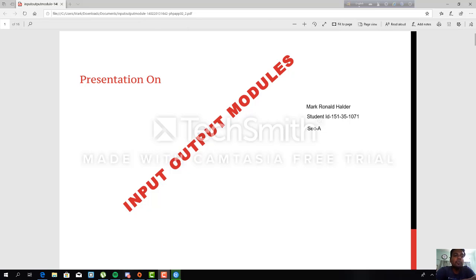There is a module called the SLC 500 combination. This combination works like this: each screw terminal will have a unique identifier called an address. Each field device input screw terminal will correlate to a status indicator. The status indicator will be on when the input point sees an input signal. The status indicator will have the same address identifier as the input screw terminal.